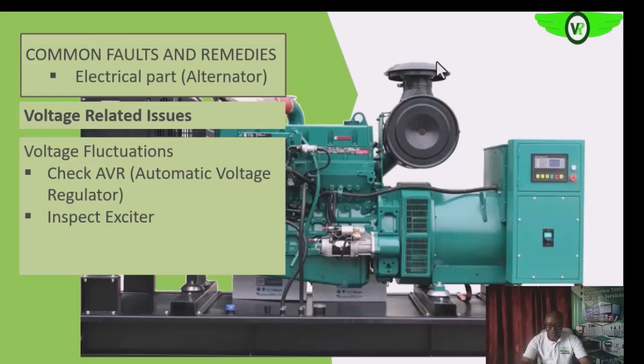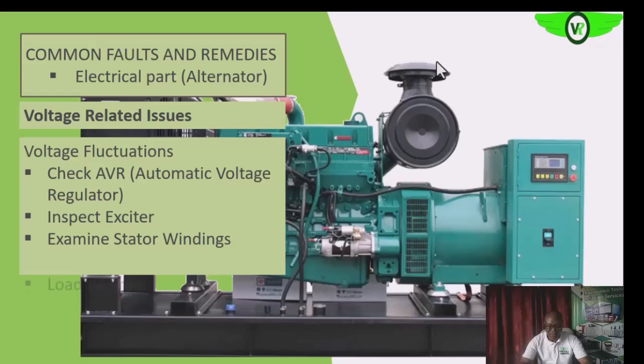We want to inspect the entire excitation system. It is also possible that the stator winding or the field winding is having problems. Since the field winding is not accessible, we want to check the stator winding — check for grounding, and if we have a provision, check the winding resistance with a low resistance meter and check continuity to ground to assess the insulation level.